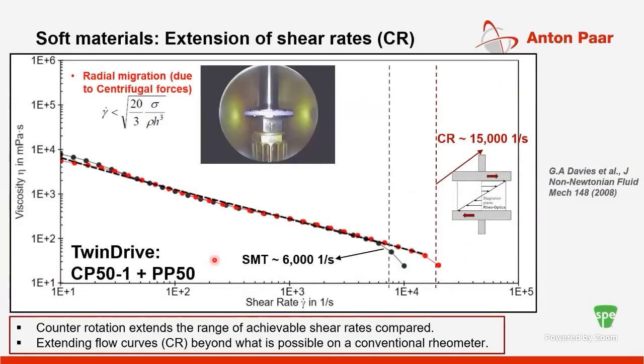Now we talked about artificial edge fracture effects. Let's talk about another experimental challenge, which is radial migration of the sample. Hopefully the video here convinces you how at high shear rates, the sample can actually migrate out of the gap. Typically for Newtonian materials, there are equations which can predict at what shear rate this would happen. This would typically depend on the surface tension, the density of the material, and the height or the gap you're using in the system.